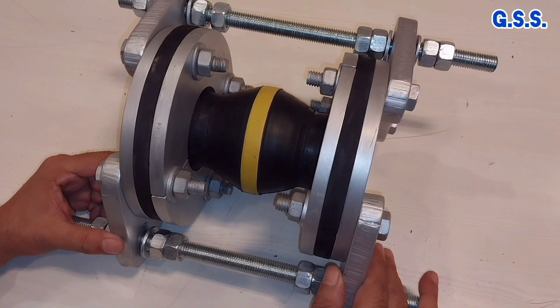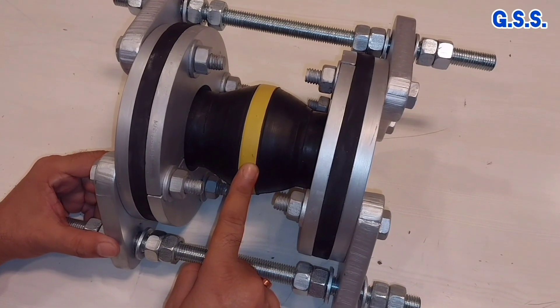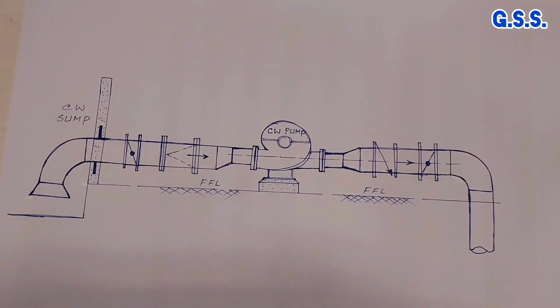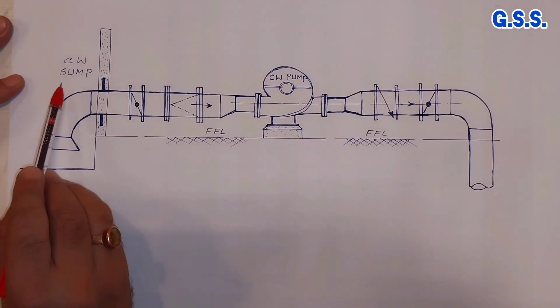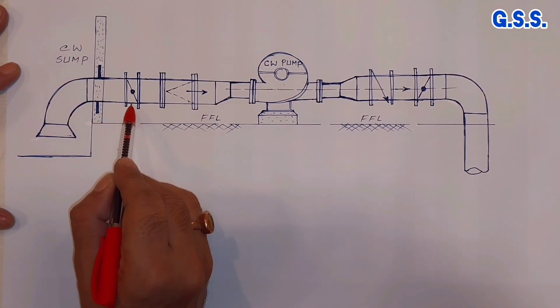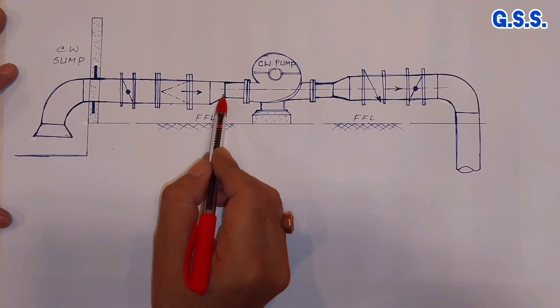Now coming to installation, this type of rubber bellows are mainly used at cooling water pump suction and discharge nozzle. Let us take an example. Suppose this is one installation of cooling water pump. This is the bell mouth, then this is suction line, first isolation valve, then strainer — this may be conical strainer or Y strainer — then eccentric reducer on suction side.